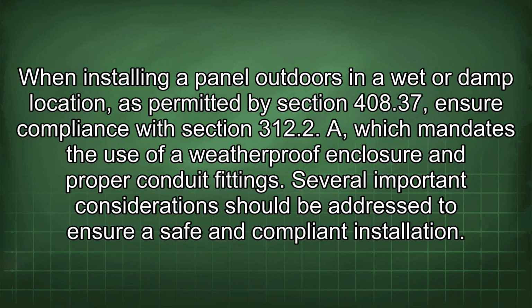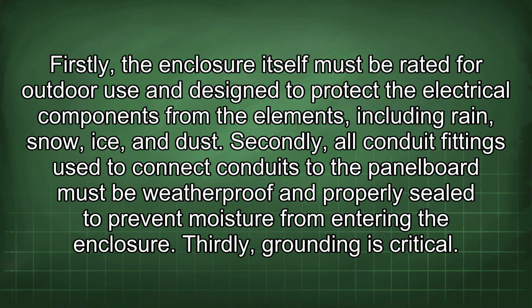When installing a panel outdoors in a wet or damp location, as permitted by Section 408.37, ensure compliance with Section 312.2(a), which mandates the use of a weatherproof enclosure and proper conduit fittings. Several important considerations should be addressed to ensure a safe and compliant installation. Firstly, the enclosure itself must be rated for outdoor use and designed to protect the electrical components from the elements, including rain, snow, ice, and dust.